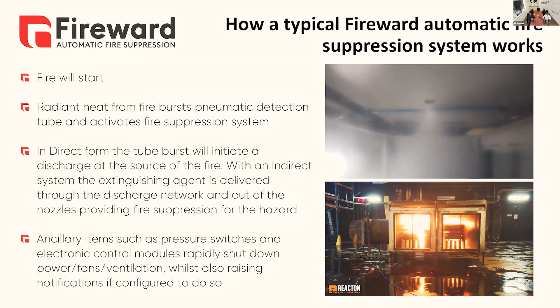And what we have in the video I'm about to play is you're going to see that we've got the simulated cooling fan running full speed. We've got a hydraulic hose leak simulated with a spray of diesel and petrol into the enclosure. And there's a timer on the left, which you can see here. And we manually activate the system at 2 minutes. We give the fire time to establish in this test. And then the system must extinguish the fire with no reoccurrences of the fire. So this is just one out of hundreds of tests that we do on the system.